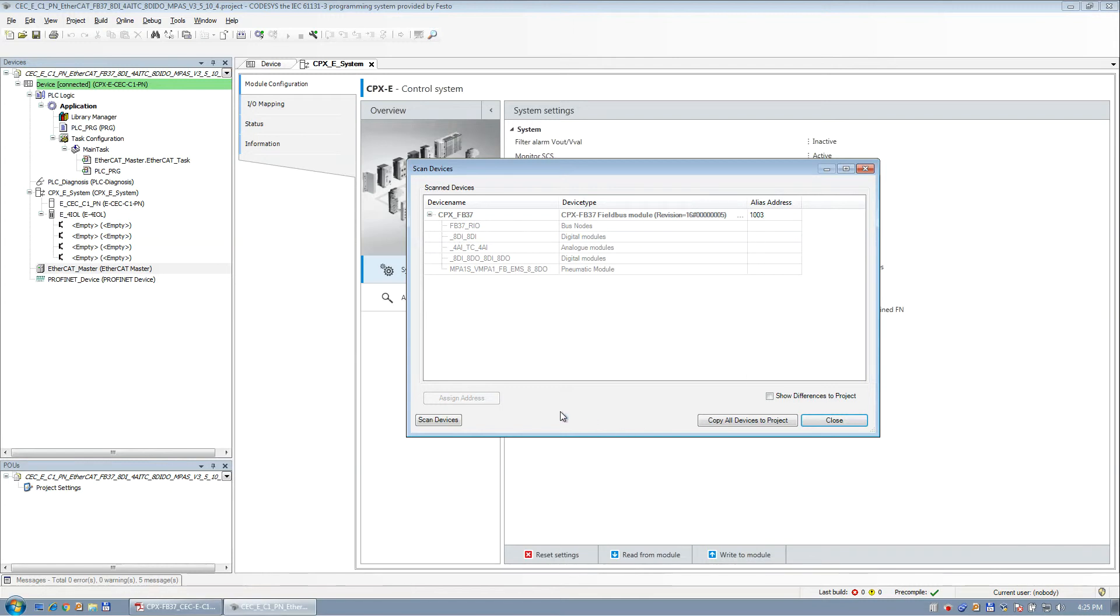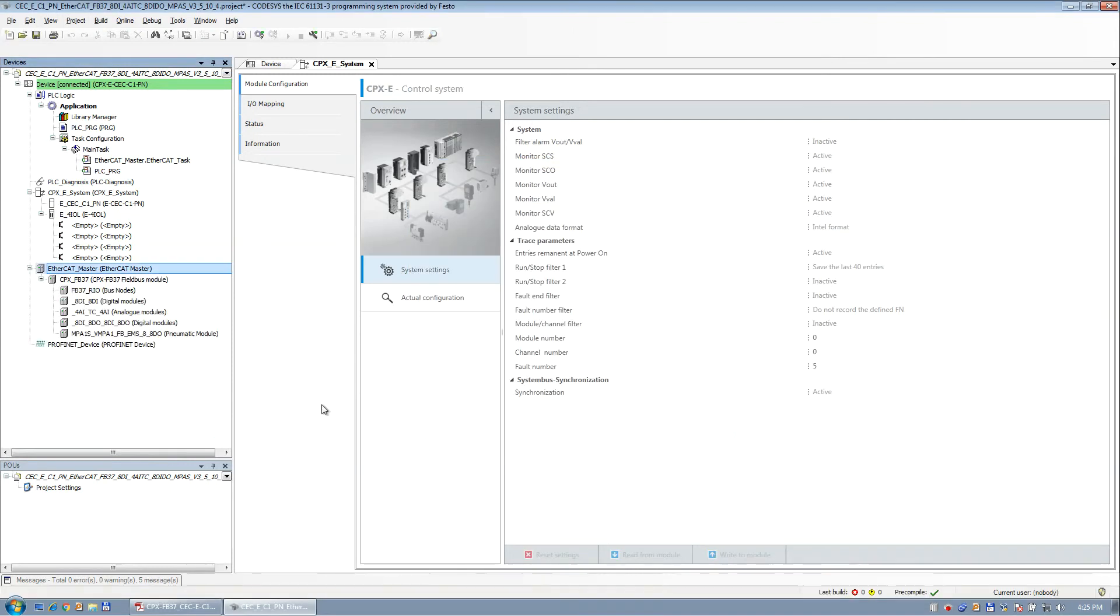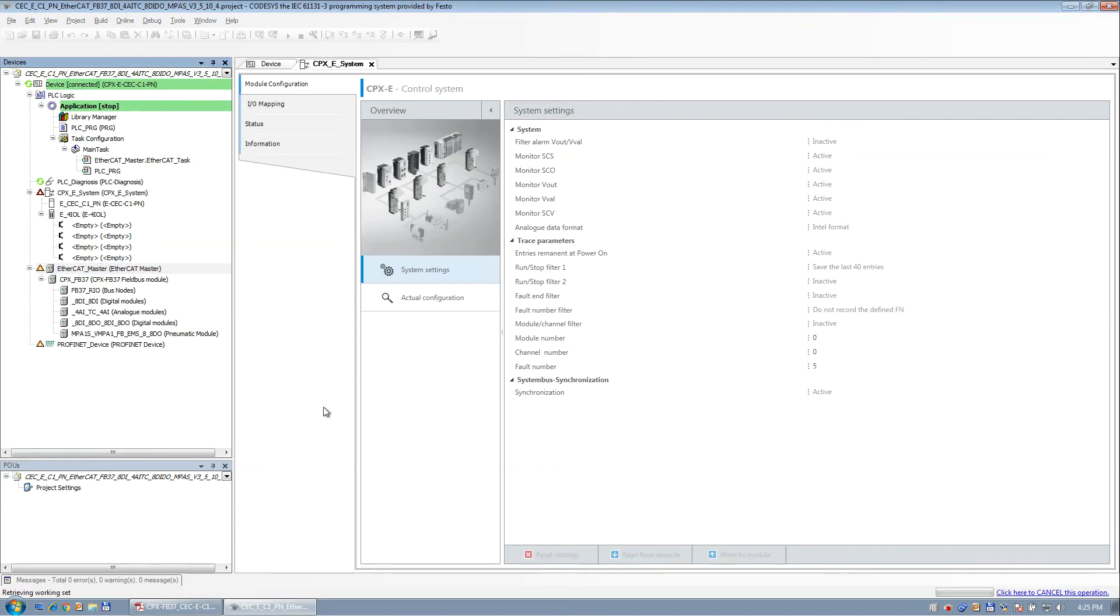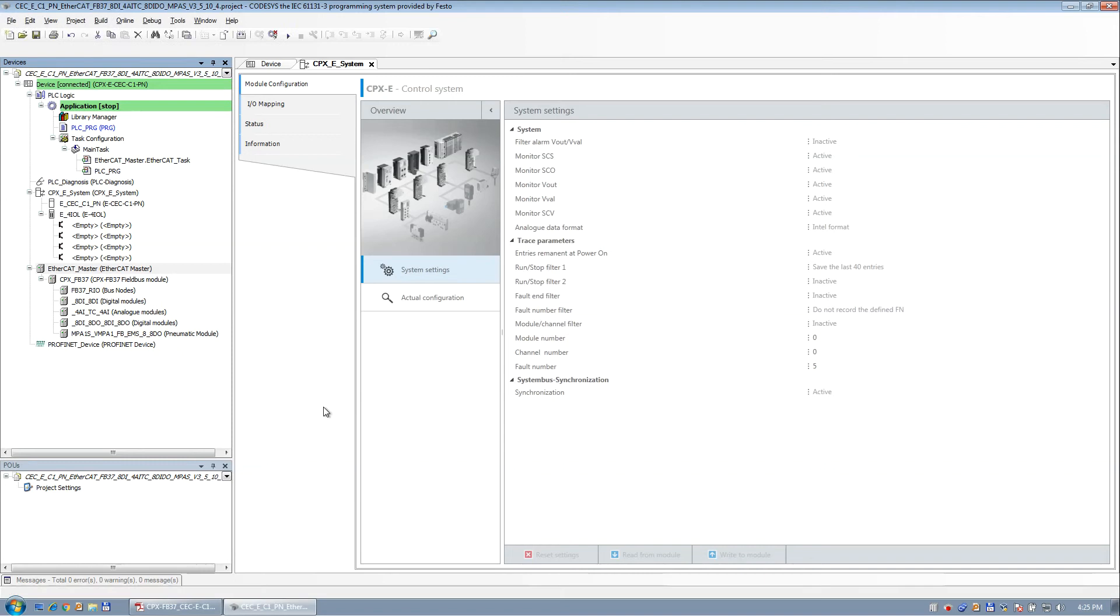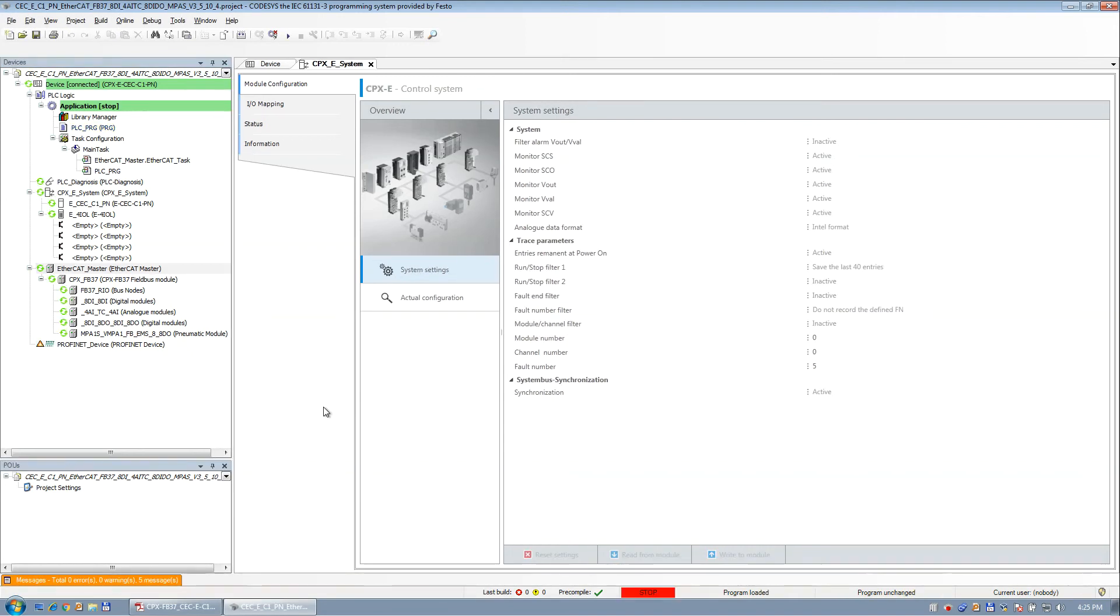So the one key thing here is if you want to assign an IP, this is an alias address. So if you want to assign an address, you basically put in an address here. You say assign, you cycle power to it, and you hit OK, and then it'll be like that. So now I'm going to simply copy this to the project and save it, download it, and we have all greens.